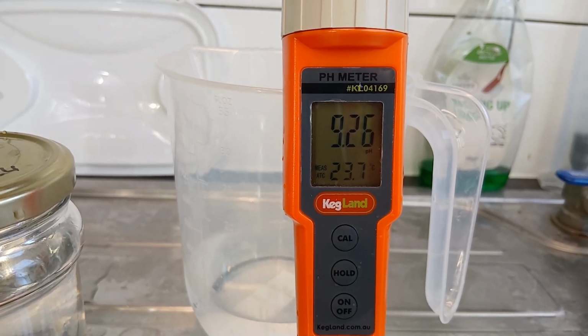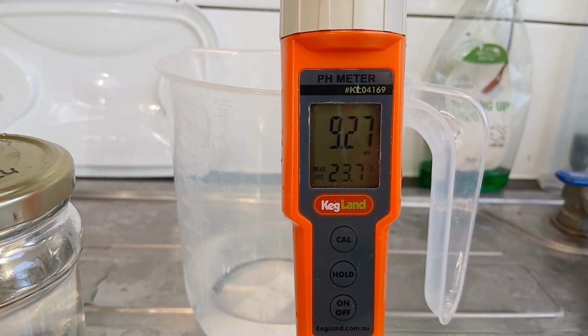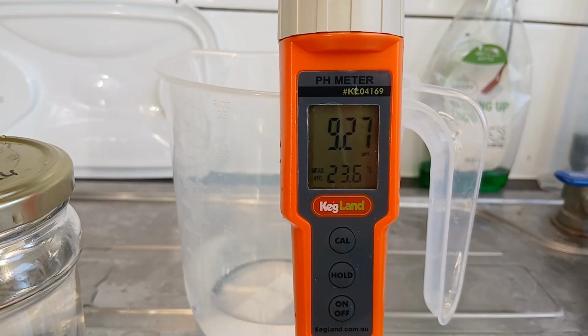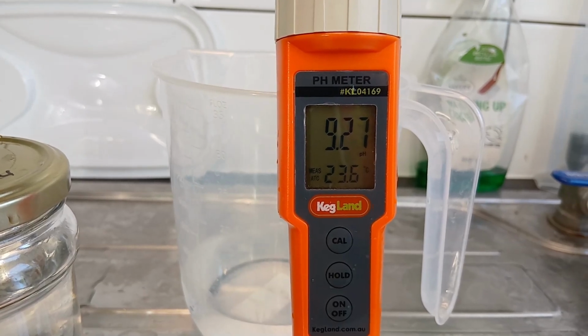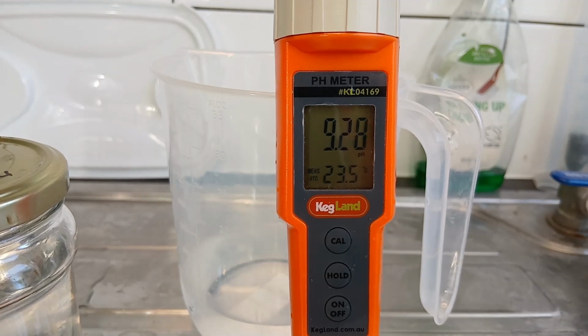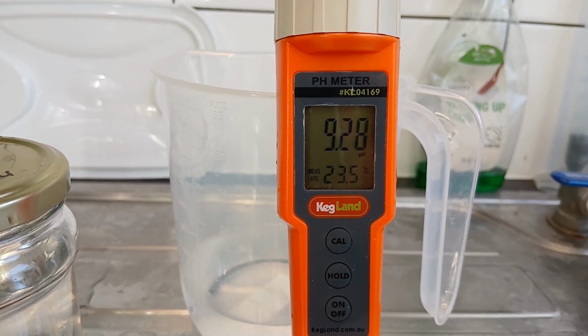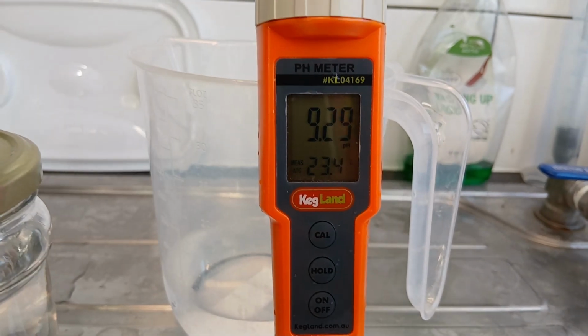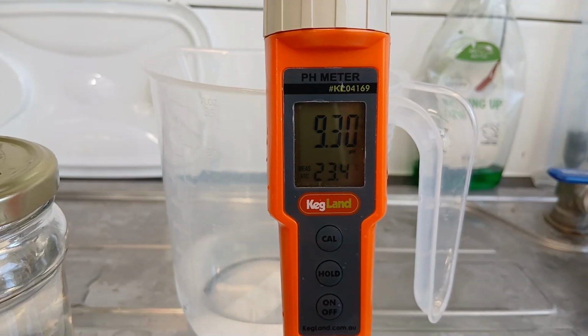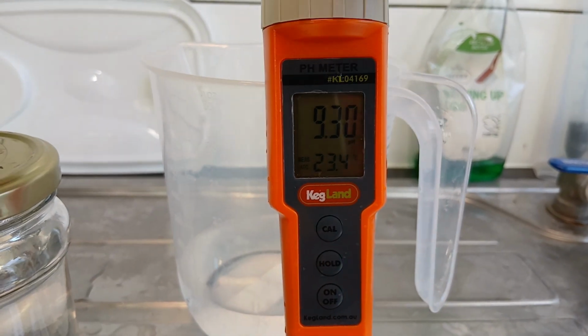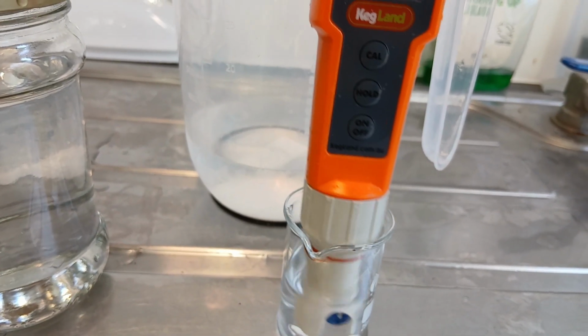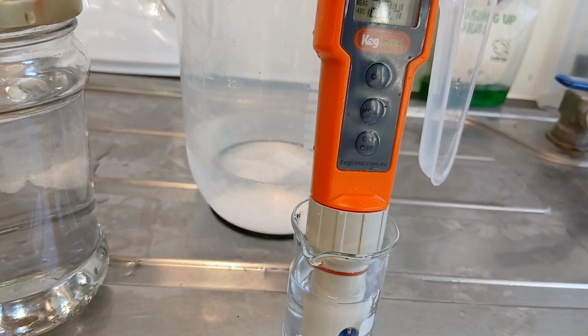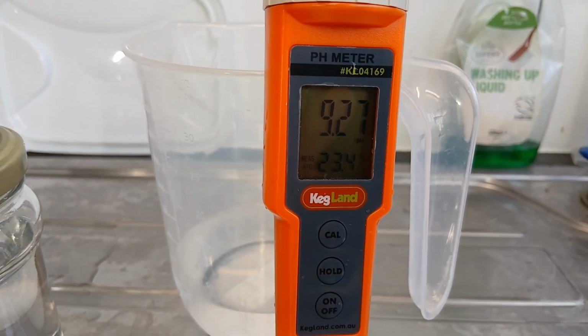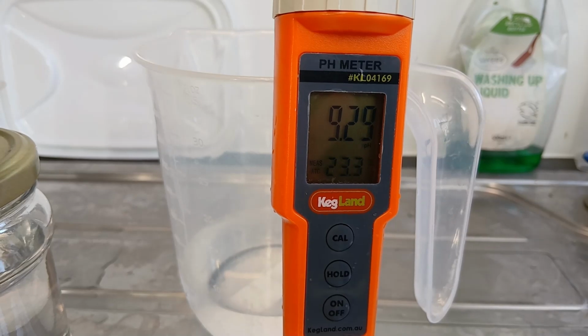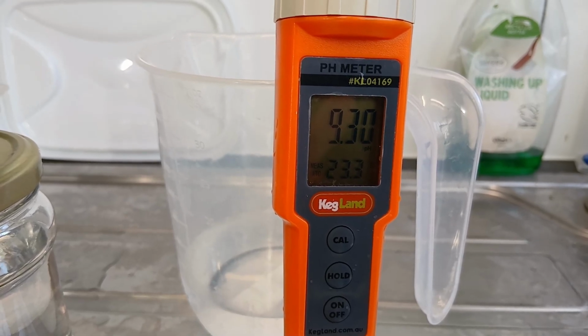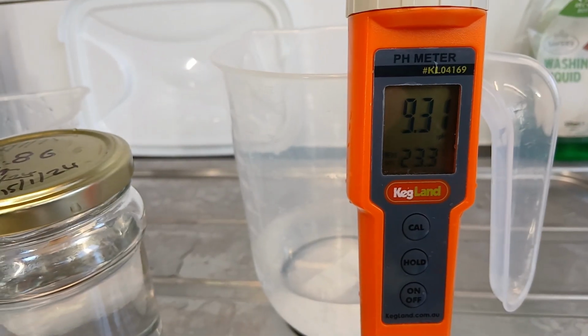Steadily rising. It's gone back up. It's flickered between 9.25, 9.26. Oh, there we go, 9.27. Still rising. 9.29, still rising there. 9.30. Just agitate the probe in the liquid a little bit, just make sure it gets all on the electrode. Okay, that's interesting. It's brought that back down. No, 9.27, 9.28. So we're stabilizing around that 9.31.